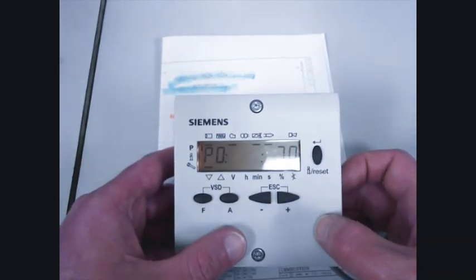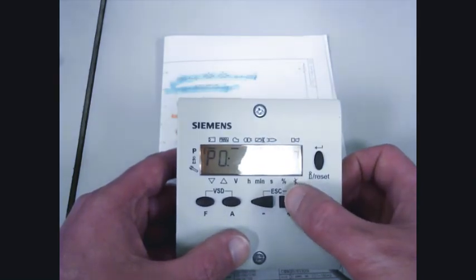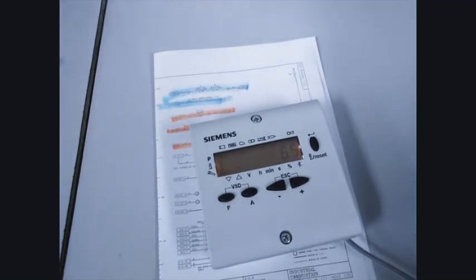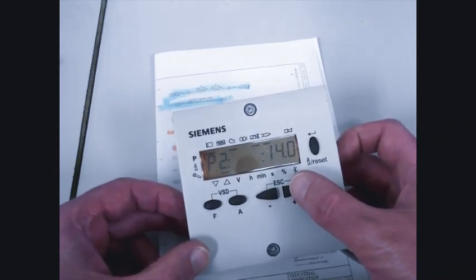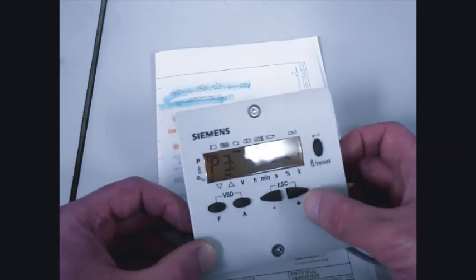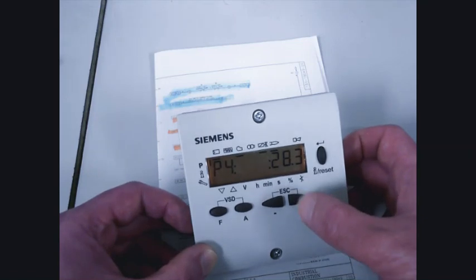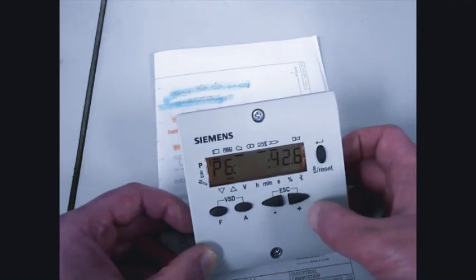P0 should also blink to confirm it is verified. Adjust these points using a combustion analyzer — target low fire at 7–9% O2 and less than 0.04% CO (400 parts per million). High fire is typically between 3 and 4% O2 and less than 0.04% CO. Set each point by letting it settle and checking the analyzer, adjusting accordingly.